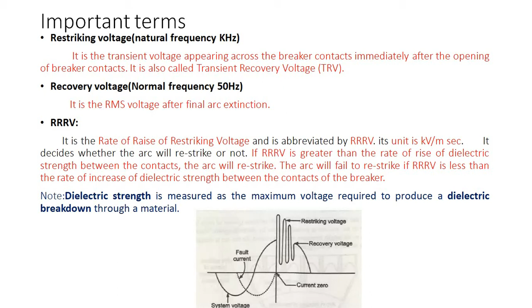The next point, RRRV. It is the rate of rise of restriking voltage, abbreviated RRRV. Its unit is kilovolt per microsecond. It decides whether the arc will restrike or not. If RRRV is greater than the rate of rise of dielectric strength between the contacts, the arc will restrike. The arc will fail to restrike if RRRV is less than the rate of increase of dielectric strength between the contacts of the breaker. Note, very important: dielectric strength is measured as the maximum voltage required to produce a dielectric breakdown through a material.